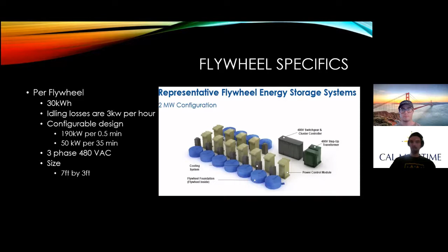They're designed in two ways: they can deliver 190 kilowatts over 30 seconds, or 50 kilowatts over 35 minutes, depending on how drastically power is needed. They typically operate three-phase 480 volts AC, which is standard. The flywheels we examined are generally 7 feet by 3 feet, but that's not a big issue since they're typically buried underground for safety.